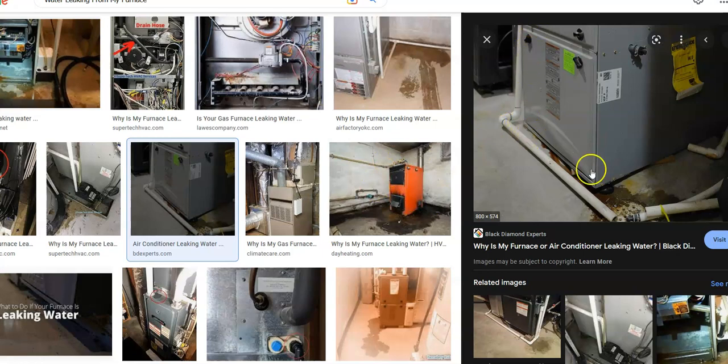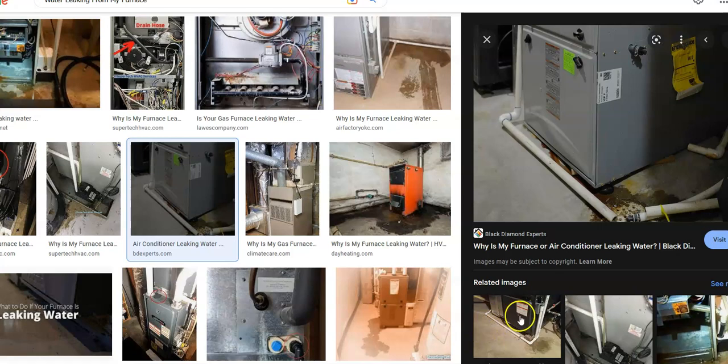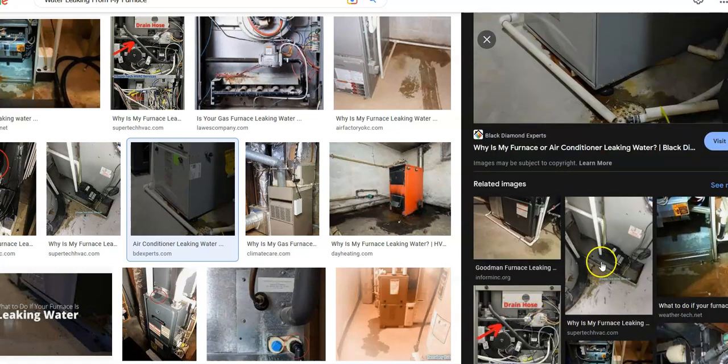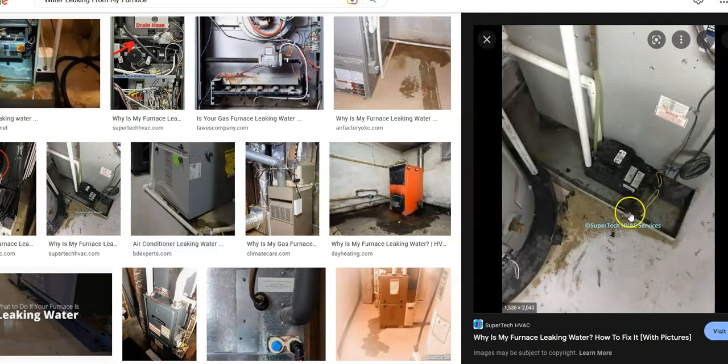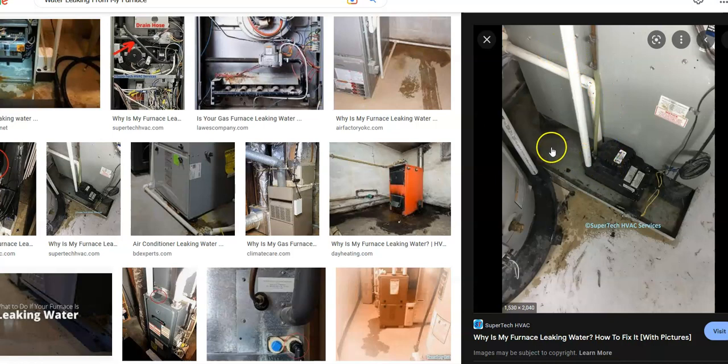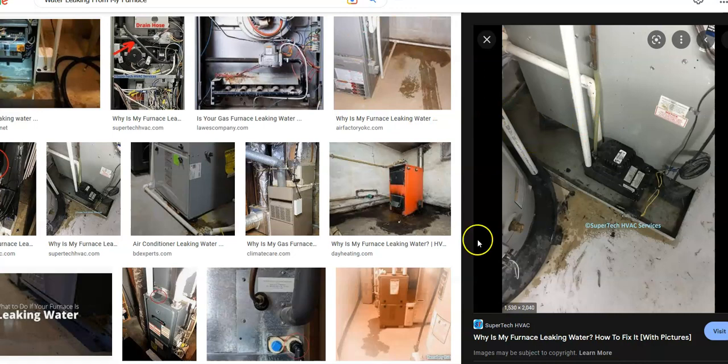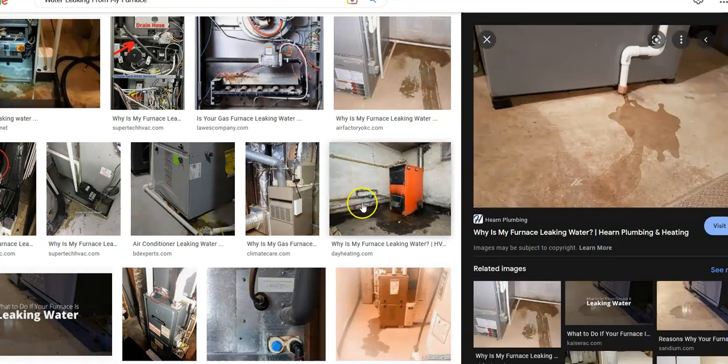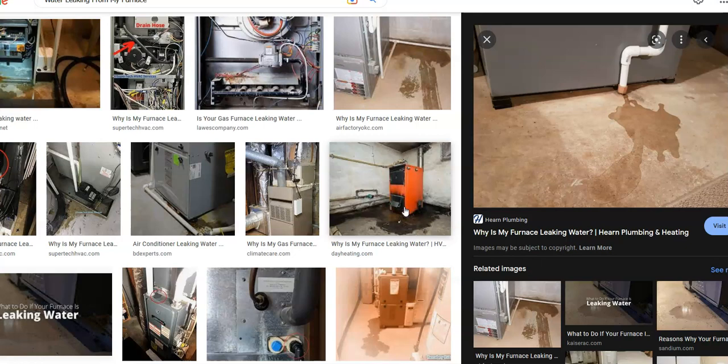Here's another image of a drain line coming down, venting out right here. There's many ways that these can be installed, so there's no set way. Right here, they even have a pump that's pumping it up. This is likely because it's inside of a basement. If you have this type of system, what it does is come down, and as soon as this fills up, the little float will trip on this pump and then it'll pump it up outside. So there's different ways that a drain line can be run. There's no set way, but basically it's just draining water.